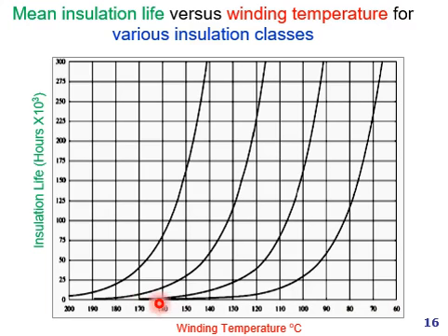So it can be seen that for a lower winding temperature the insulation life is larger. So the insulation life can be prolonged by reducing the winding temperature.